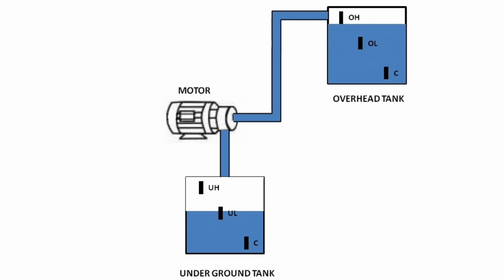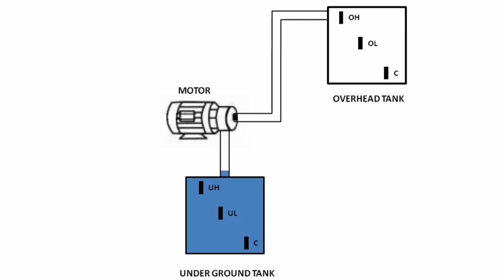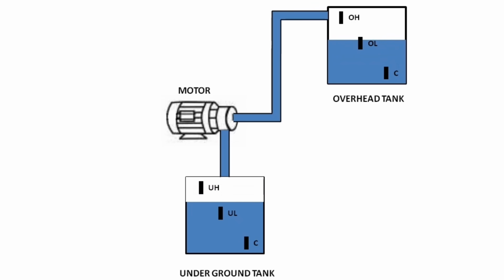This model comes with 6 sensors. You need to put 3 sensors in the overhead tank and 3 sensors in the underground tank. When the water level of the overhead tank becomes low, meaning the water gets down from the middle sensor, and water is present in the underground tank or sump, the motor starts automatically. The tank starts filling up. When the water level reaches the higher level, the motor automatically switches off. Auto off when the tank is full or the sump is empty.